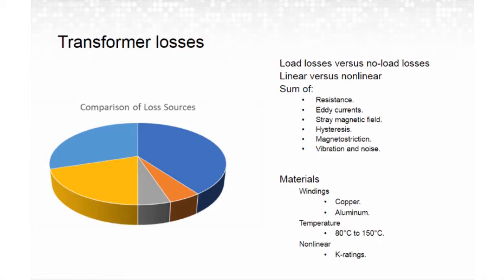Now, characteristics that designers can choose to impact the magnitude of these losses include the winding material, the temperature rise rating, and a nonlinear rating. For example, the choice of copper or aluminum windings affects the winding resistance. Temperature rise rating design affects both load and core losses. Common temperature rise ratings are 80, 115, and 150 degrees Celsius. And which selection is the most efficient depends on the loading. Now, this rating also affects the physical size of the transformer and the heat load that will be generated.